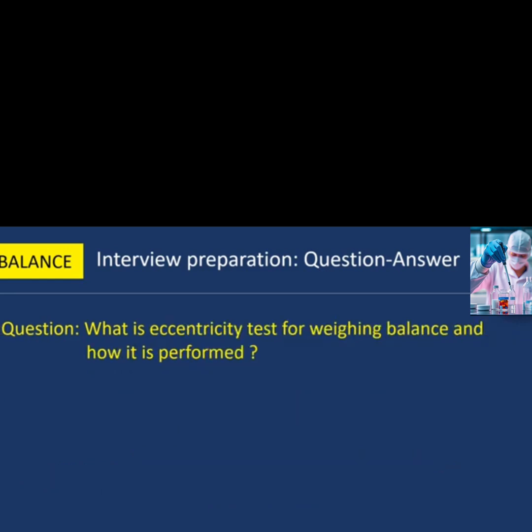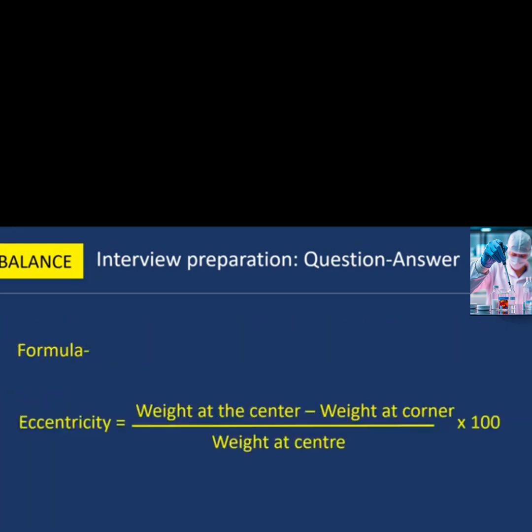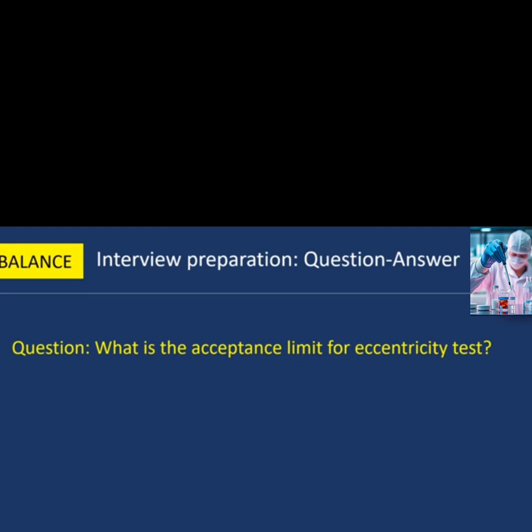Next question: what is the eccentricity test for a weighing balance and how is it performed? For the eccentricity test, a weight more than 30% of the balance capacity is selected and placed at the center and all corners of the weighing pan to check eccentricity. As shown in the figure, 5 positions are used: position 1 is the center, and positions 2, 3, 4, and 5 are the corners. Formula: Eccentricity = (Weight at Center − Weight at Corner) ÷ Weight at Center × 100. The acceptance limit for the eccentricity test is not more than 0.05%.